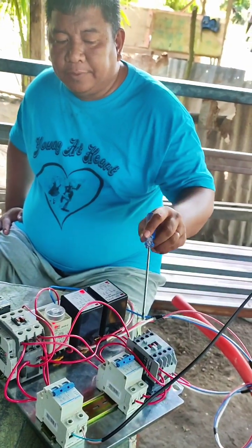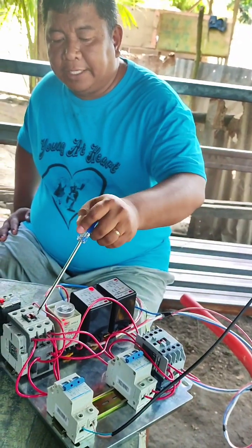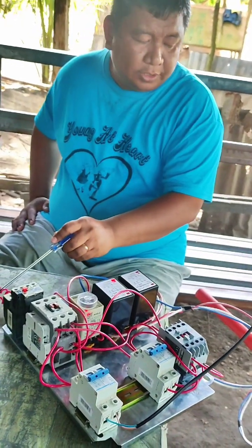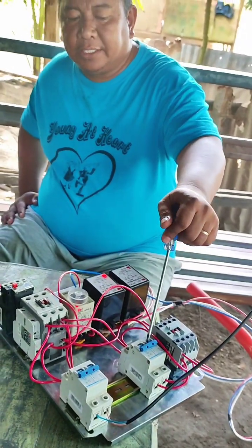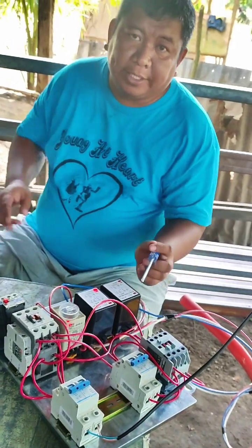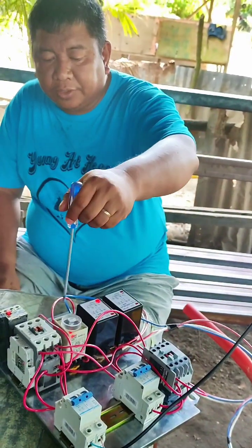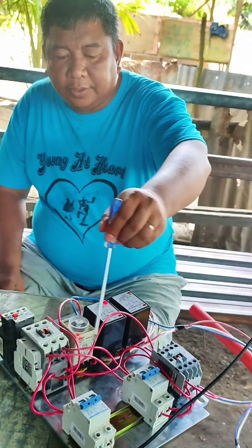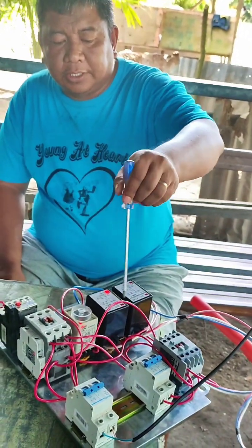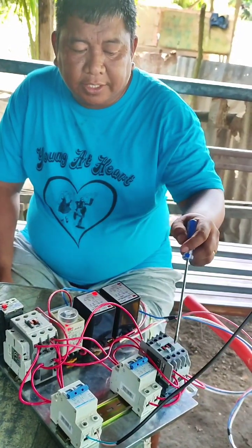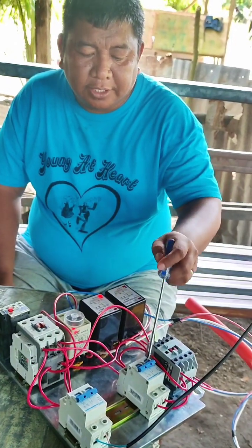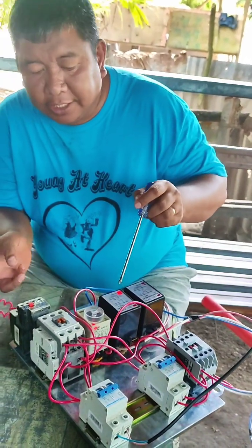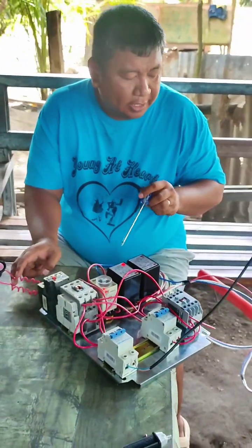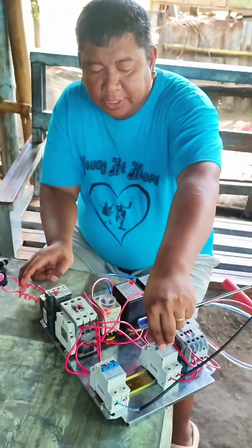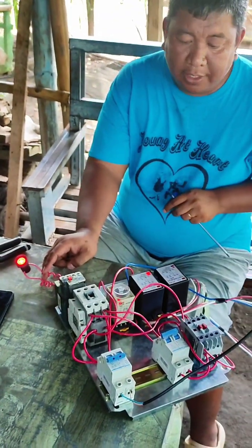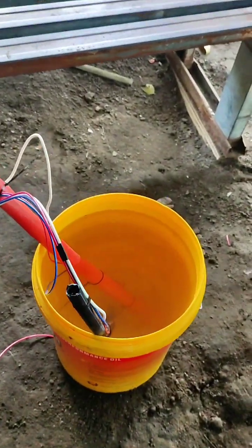It is being wired up to this magnetic contactor, which is connected to the main power line, and this contactor switches this on. This breaker works as an alternating contact for automatic and manual. This system here is automation, and this system could be run on manual mode. Say for example this automation failed. This is triggered by this contactor. If it's on, then the automatic engages, and when you put this off, it engages the manual. So here is the simulation for the water tank and the water well.